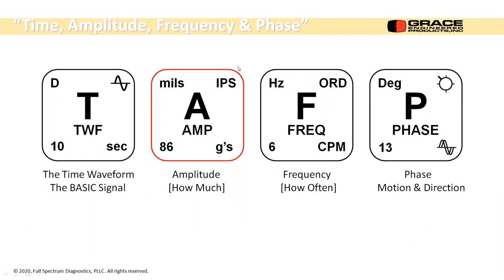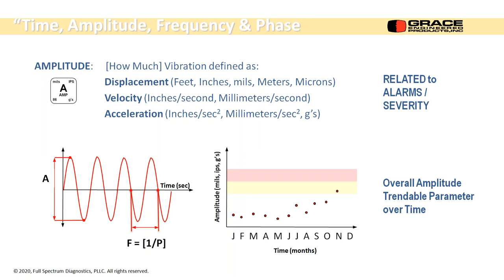Okay. We're going to talk about amplitude first. Amplitude is how much, it's severity, it's where we start off. So the first thing we're going to do when we have one of these transducers installed, and I'm just showing one direction here, but really you're getting X, Y, and Z, and you'll get three trends, is pull out the time waveform. We have some algorithm inside the logic of the transducer that stores the highest amplitude, and that's what we see in our trends. We use this amplitude to set new alarm levels. So this might be an alarm level based on my chart of rules of thumb, 0.35 inches per second, when it runs down here somewhere.